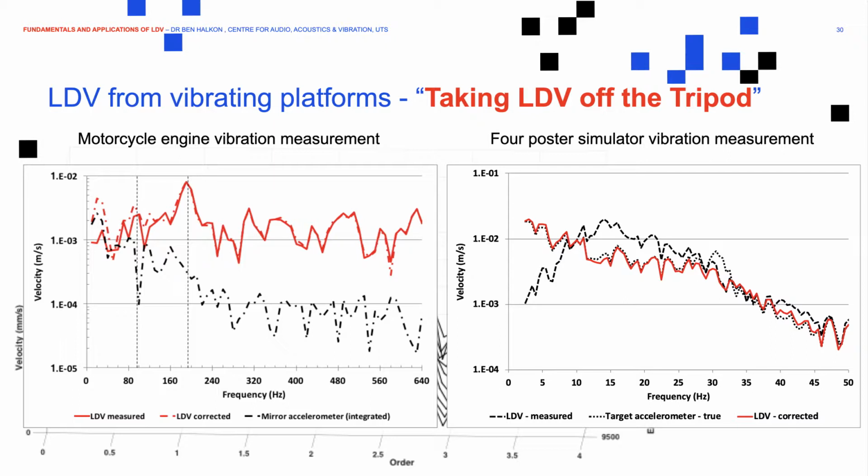And then we can do that with the traditional waterfall spectrum, and we can see the evolution of the half order peak and the 1 times order peak as we increase in engine speed through a sweep.